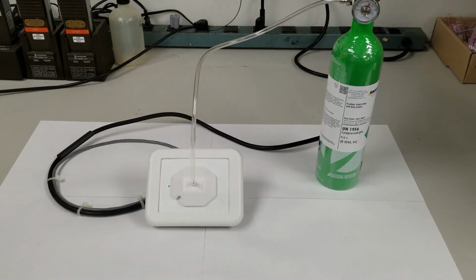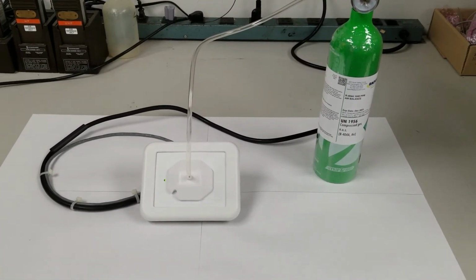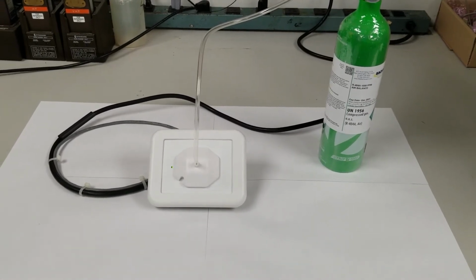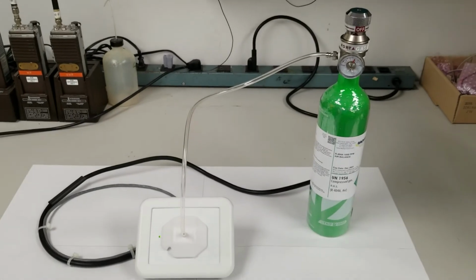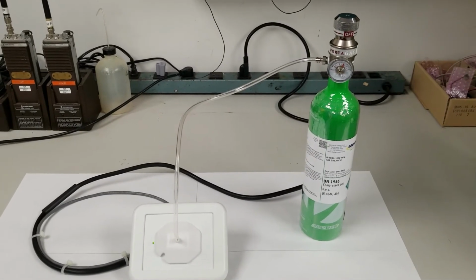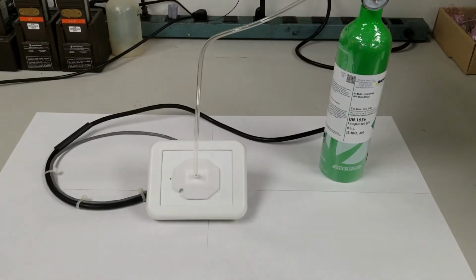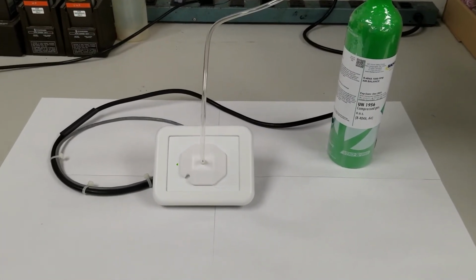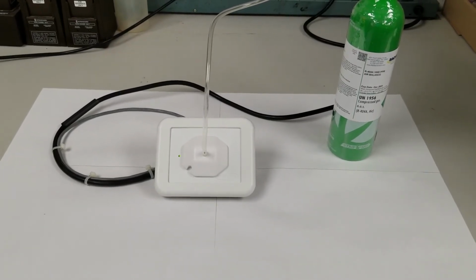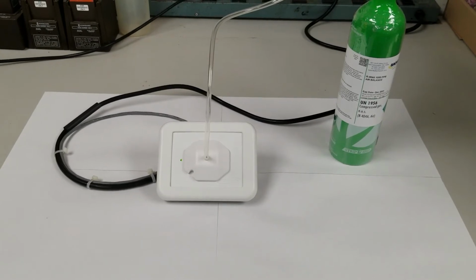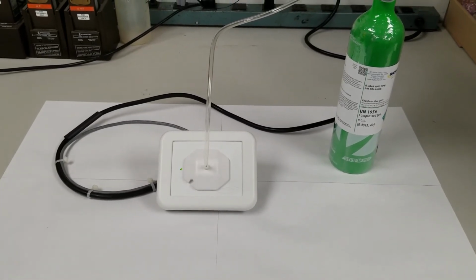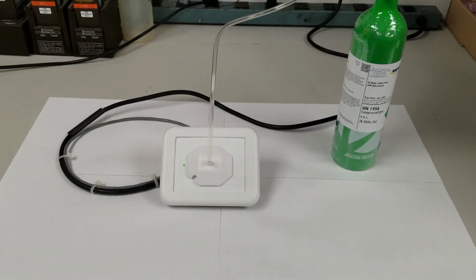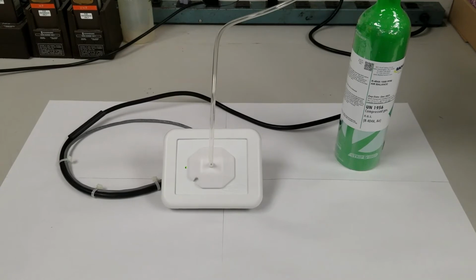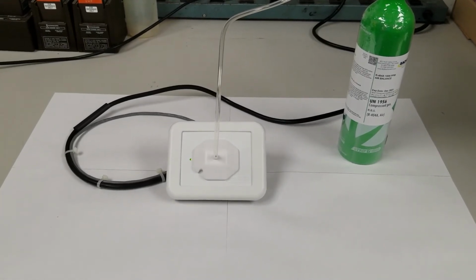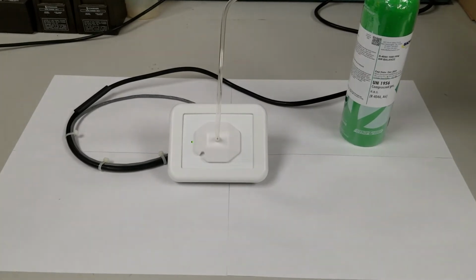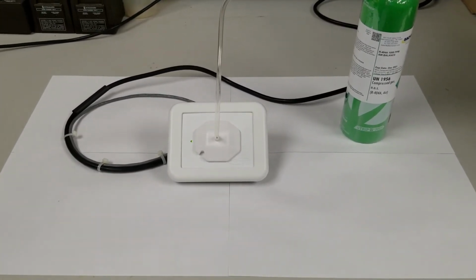Okay, here we're going to do the span calibration using 404A on an MVR-300. We have the cal cup with hose to a 0.3 liter per minute regulator on our gas bottle. We're going to be using mag switch 2. We're going to initiate with mag switch 2, start the gas, and confirm that the gas is flowing with mag switch 2. The LED sequence will be green orange this time, and it will go green orange, orange, etc., through 5 oranges, and then we will be finished with the span calibration.